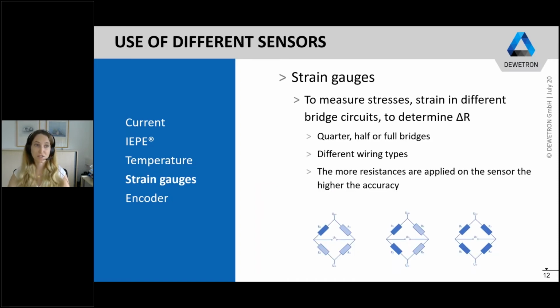The next sensor I would like to mention are strain gauges, which are used to measure stresses and strains in different bridge circuits to determine delta R. So different bridge circuits are used, and the more resistances are applied on the sensor, the higher is the accuracy. For example, for half and full bridges, the transverse and the longitudinal elongation can be measured. It is really important to consider that there are different wiring types for those bridge circuits, for example, to compensate lead and temperature resistances. So it is important to consider this whenever you want to use strain gauges for your application, that the hardware and the measurement system supports the wiring type which you would like to use.